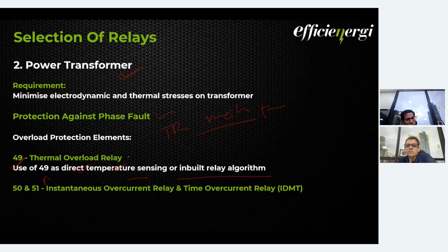On the HV side, we normally go with this relay. 49 thermal is required because insulation damage should be protected, not for the short circuit only, but for the overload also. So it is a replica of the temperature sensor. And the thermal overload relay, you can set below your stator damage curve for thermal overload.